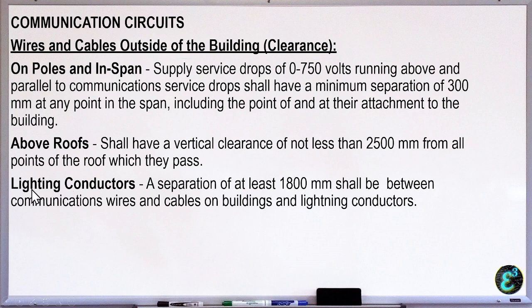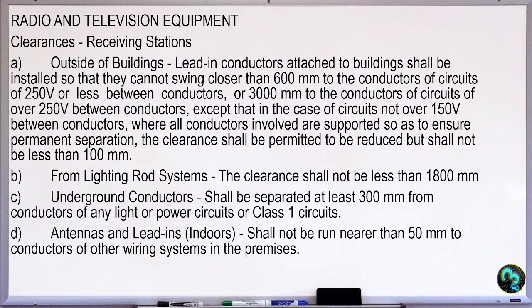Then, lighting conductor. A separation of at least 1,800 mm shall be maintained between communication wires, cables on buildings and lightning conductors. For the radio and television equipment, so clearances on receiving station. So if outside the building, the lead-in conductor attached to the building shall be installed so that they cannot swing closer than 600 mm to the conductors of circuits of 250 volts or less between the phase conductors. Tapos 3000 mm to conductors over 250 volts between, except that in case of circuits not over 150 volts between conductors where all conductors involved are supported so as to ensure their permanent separation. So for this one, mayroong mga spacer in which the spacer shall not be less than 100 mm.